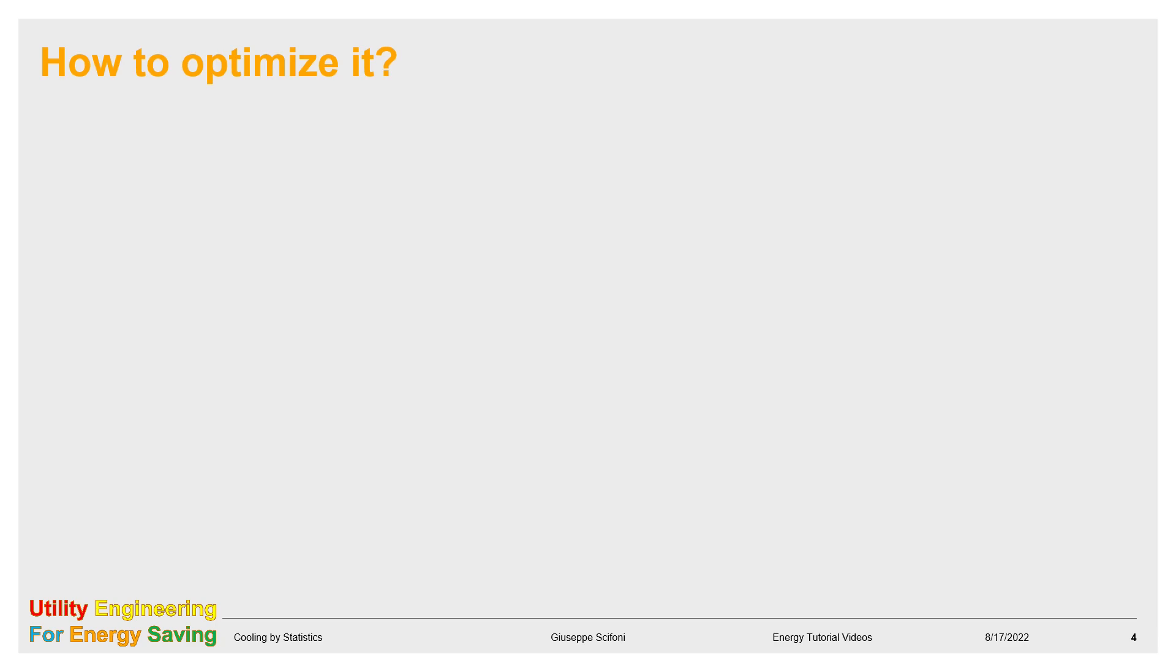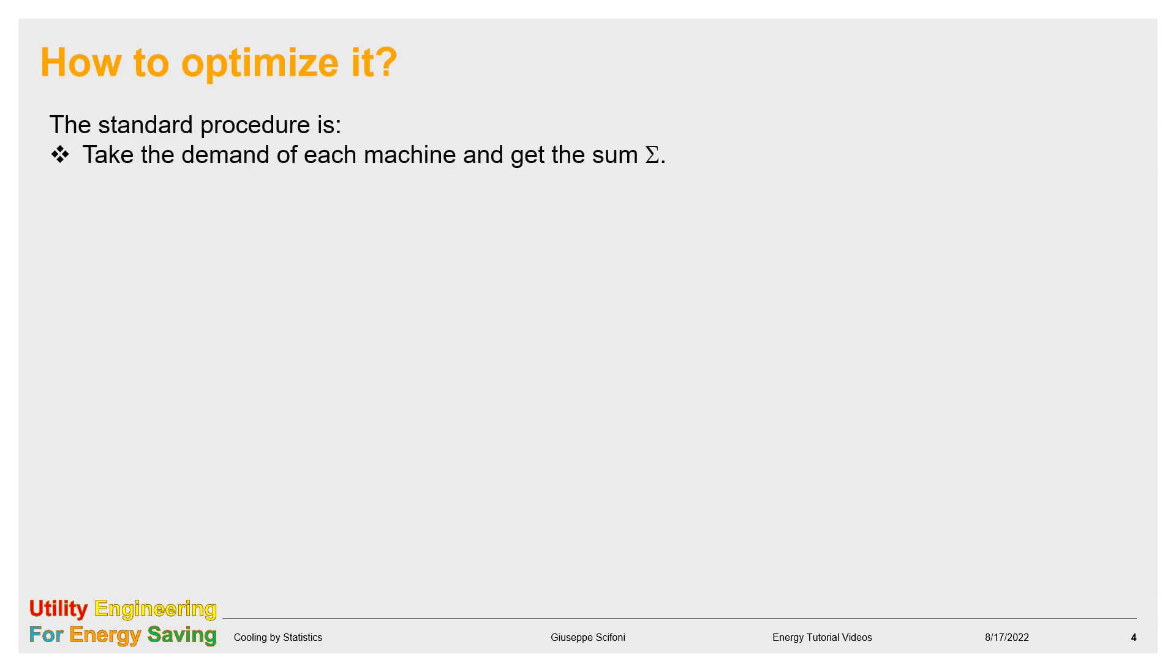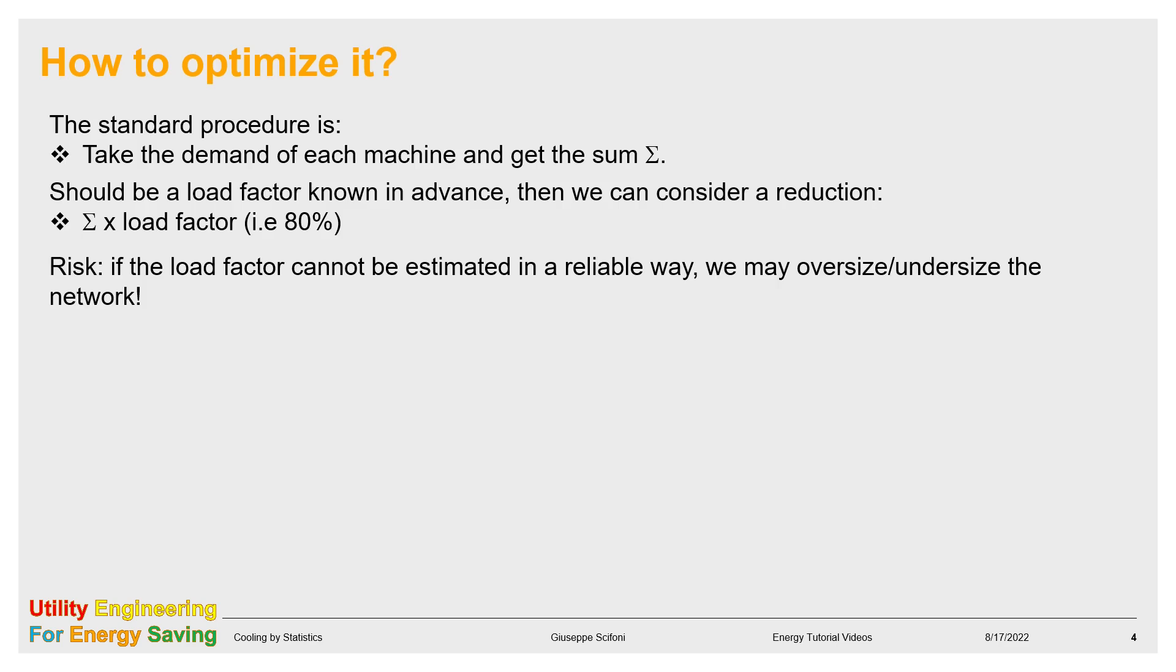The standard way to proceed, where no information about working times is available, is just to add the capacities. Should a load factor be known or estimated, the above sum can be reduced accordingly. However, we still have the risk to oversize or undersize the network if such estimation is not correct. In this presentation, we want to give you a professional tool for the estimation of such a load factor, or in other words, how the proper size can be chosen by means of statistics.